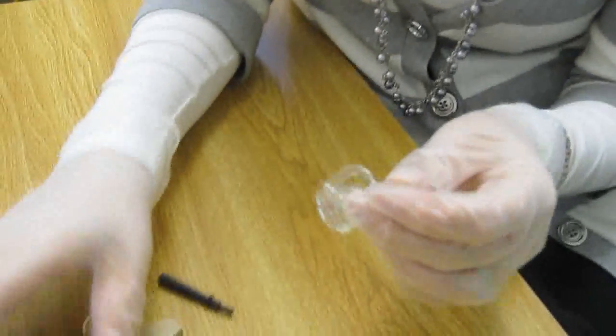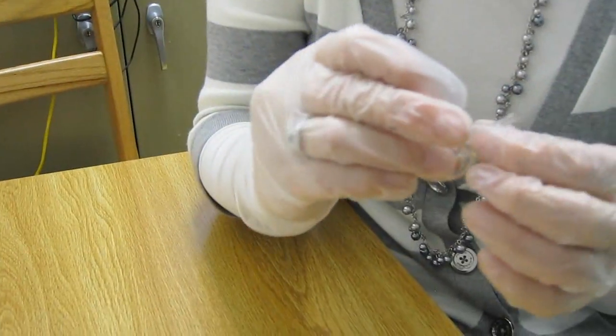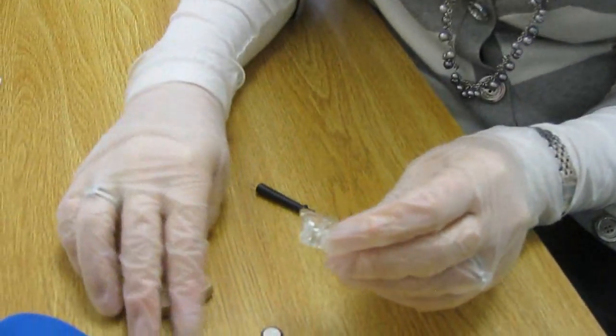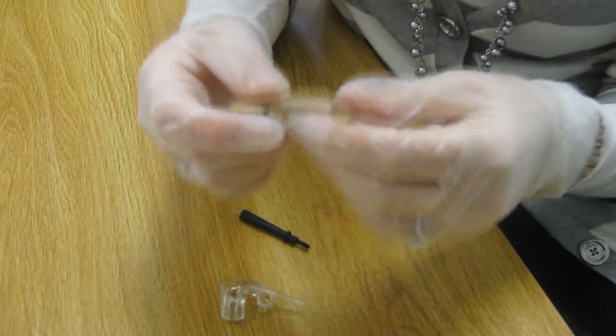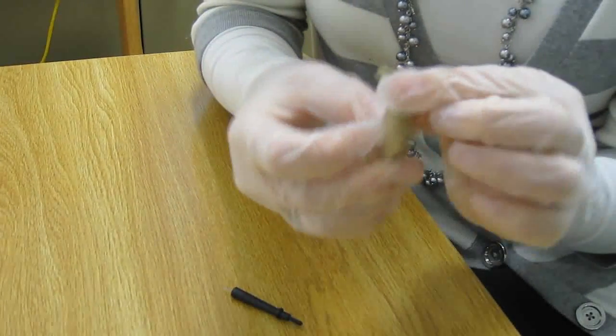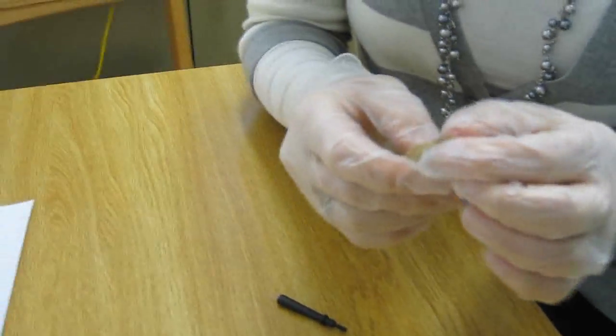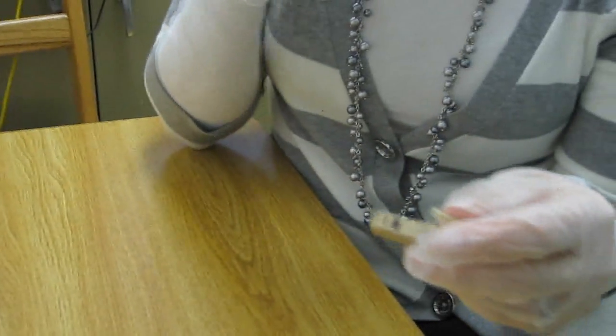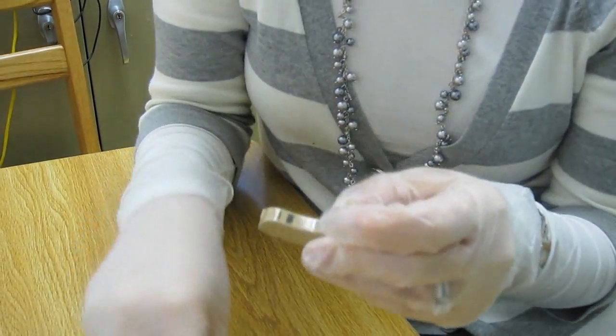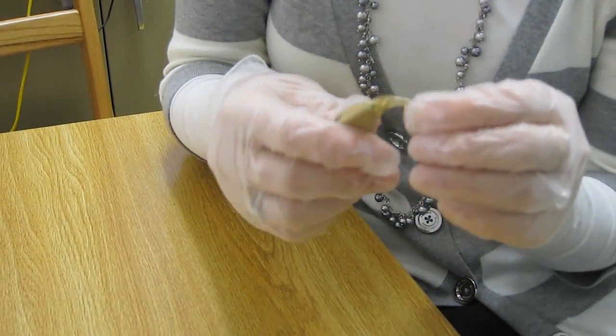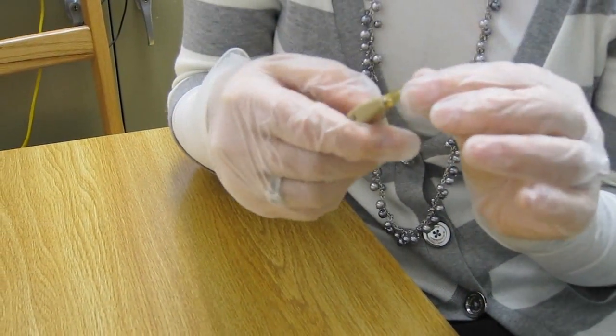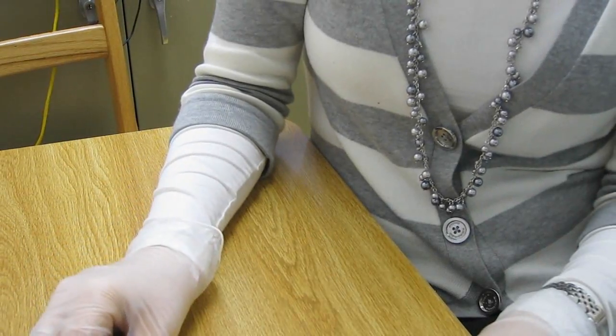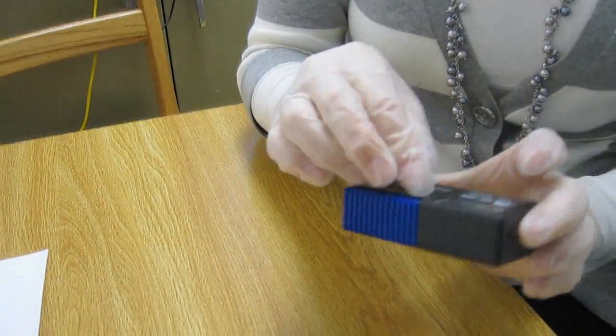So then we look to see if the tubing is yellowed and hardened, but it isn't. So next we check the ear hook to see if it's securely fastened on, and it is. Check if it's clogged with moisture or cerumen. It doesn't look like it, but we'll just check just in case. Okay, it looks good. So you check it for any discoloration. It is a little bit yellow, but it looks like it's fine. Now we're going to check the battery. So this is the correct size battery for this hearing aid. We check and you see that it's good.